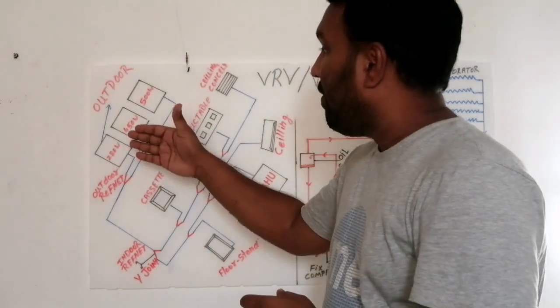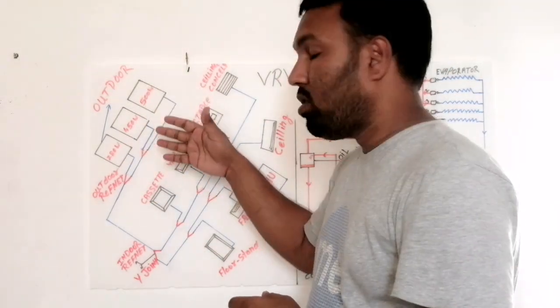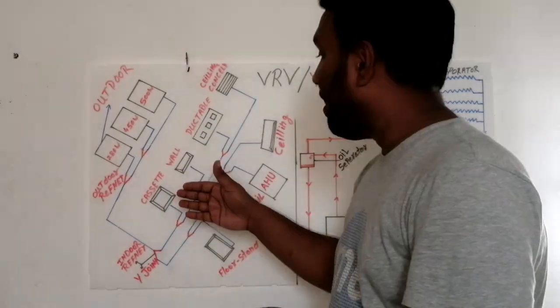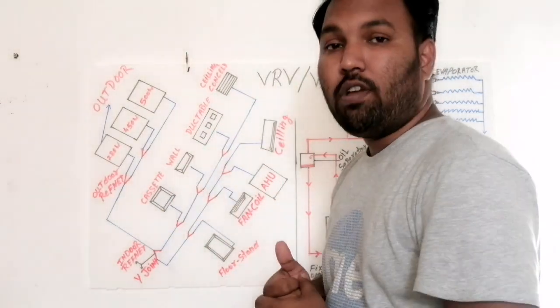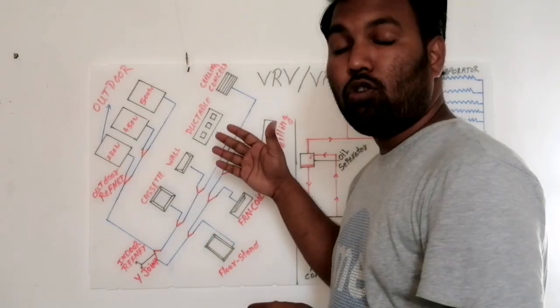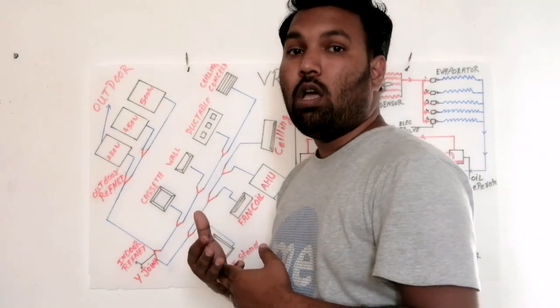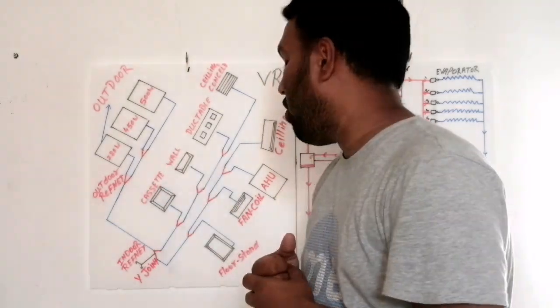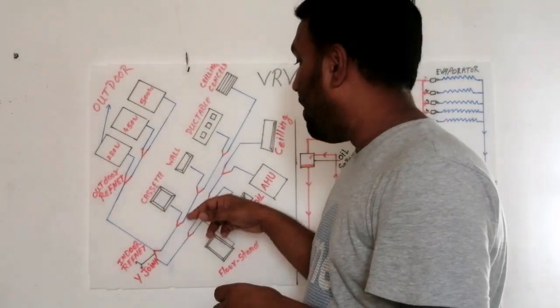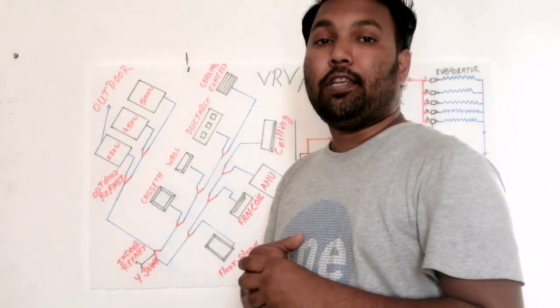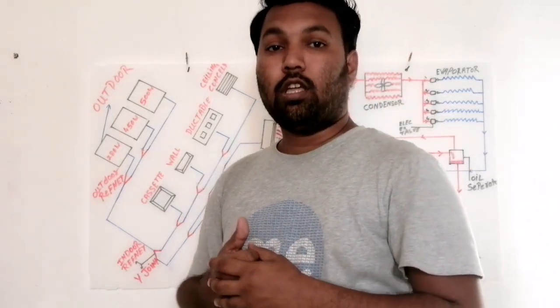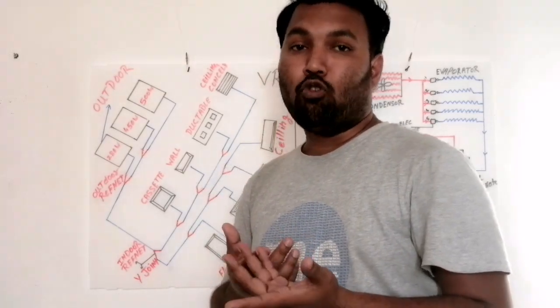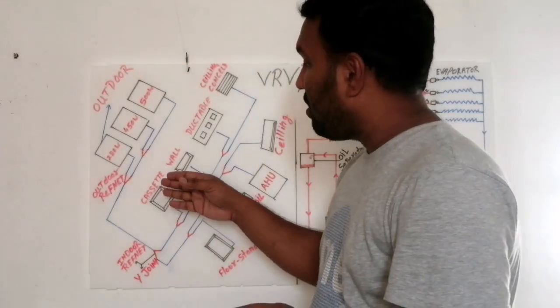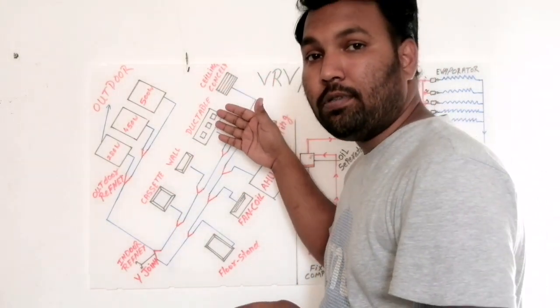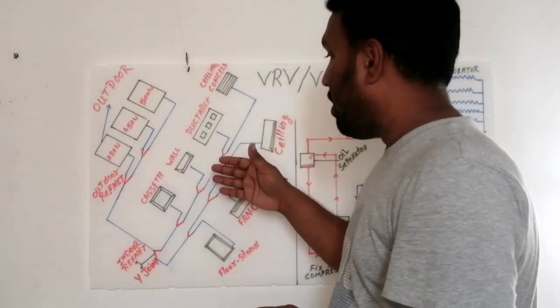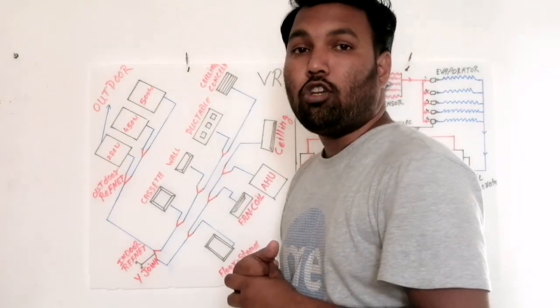As you can see here, we can connect multiple compressors in one VRV or VRF system, and we can connect different types of indoor units. A maximum of 60 indoor units with different capacities and different models can be installed in one VRV or VRF system. The maximum length of piping can be up to 150 meters, whereas in normal air conditioning the maximum copper piping is up to 15 meters. You can see here the different models, capacities and types of indoor units connected to one single VRF circuit.